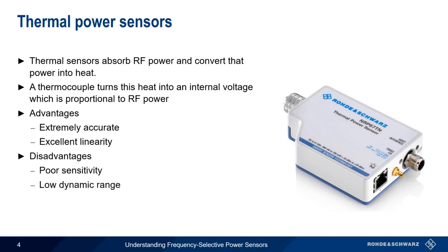Thermal sensors do, however, suffer from a number of disadvantages. The most serious of these is poor sensitivity, meaning that thermal sensors can only be used to measure relatively high power signals. They also have a small dynamic range and lower measurement speed.